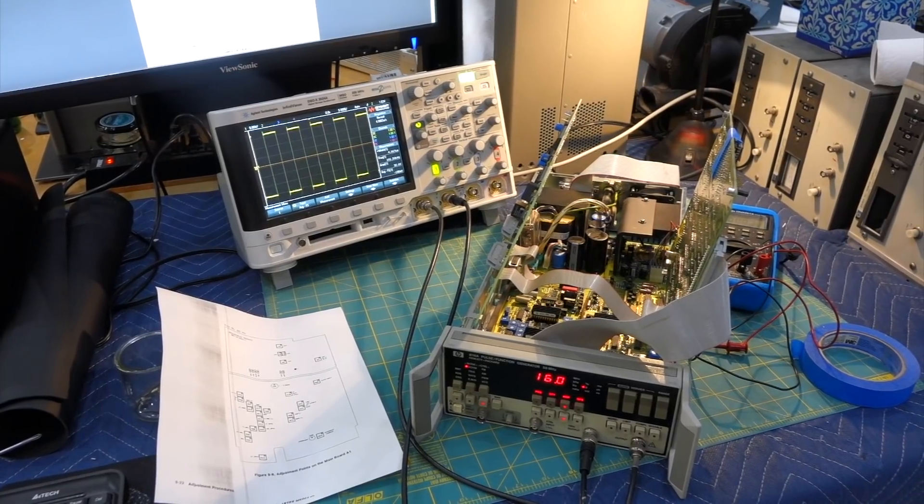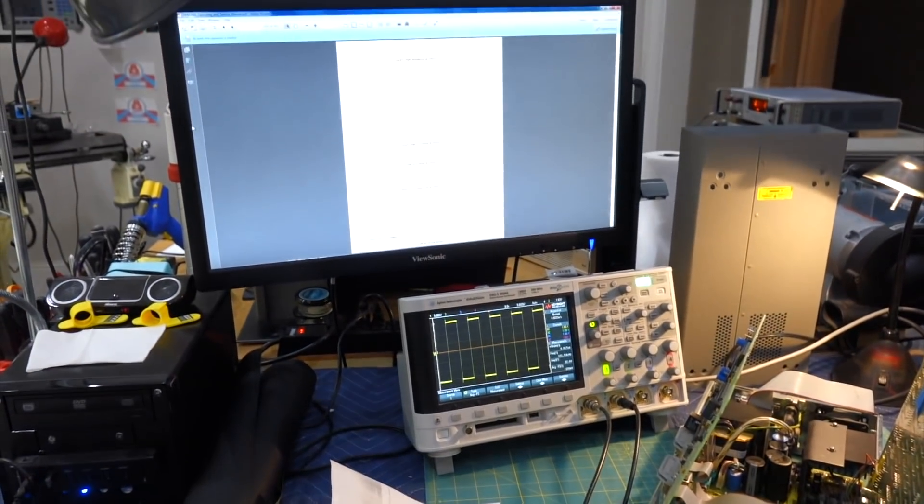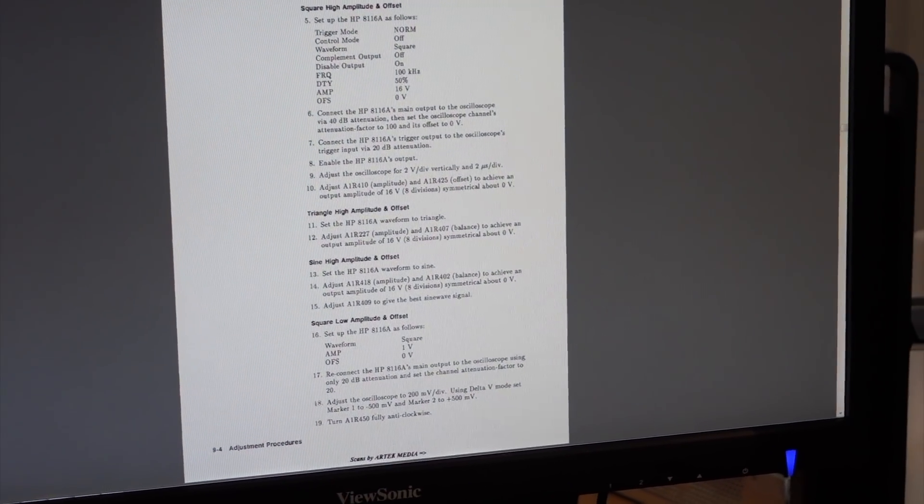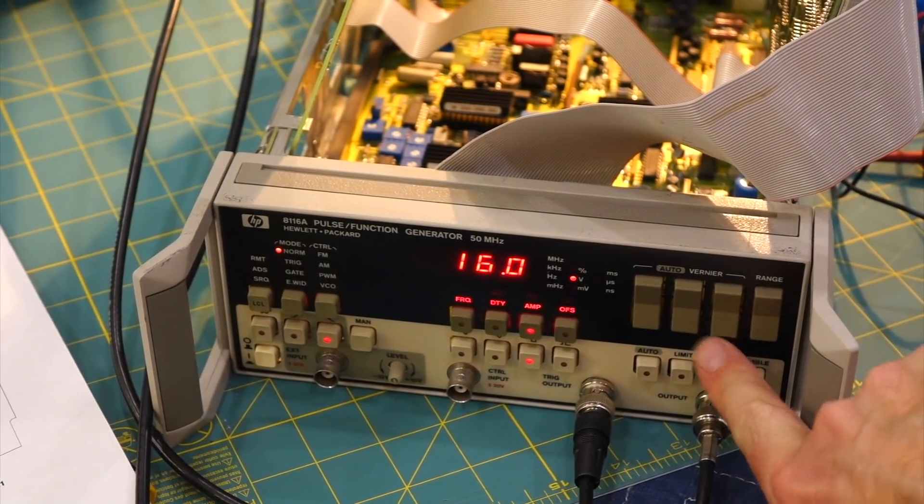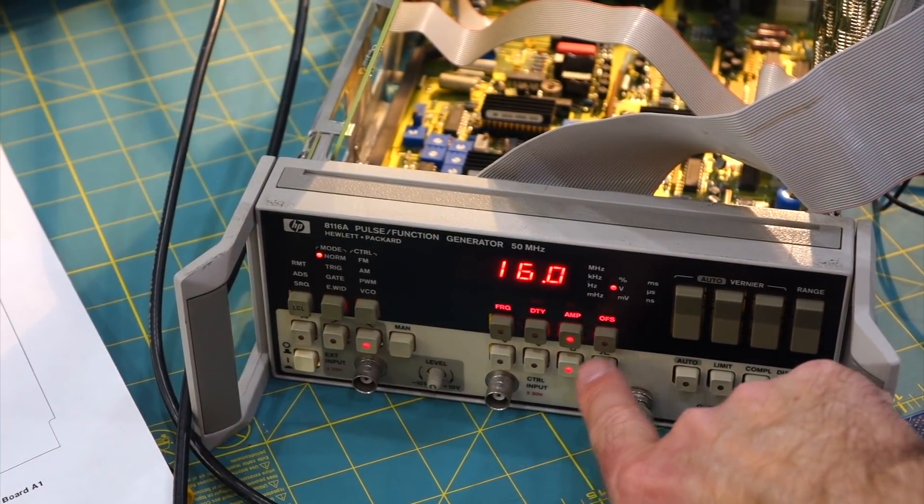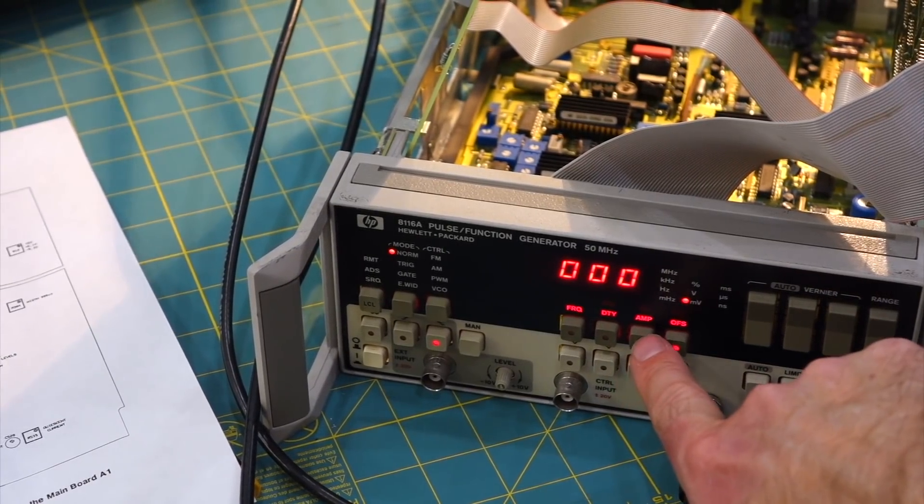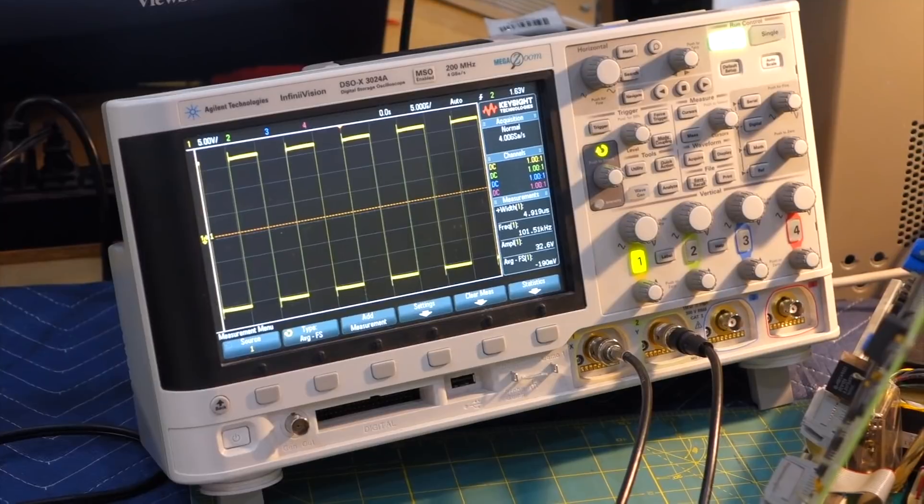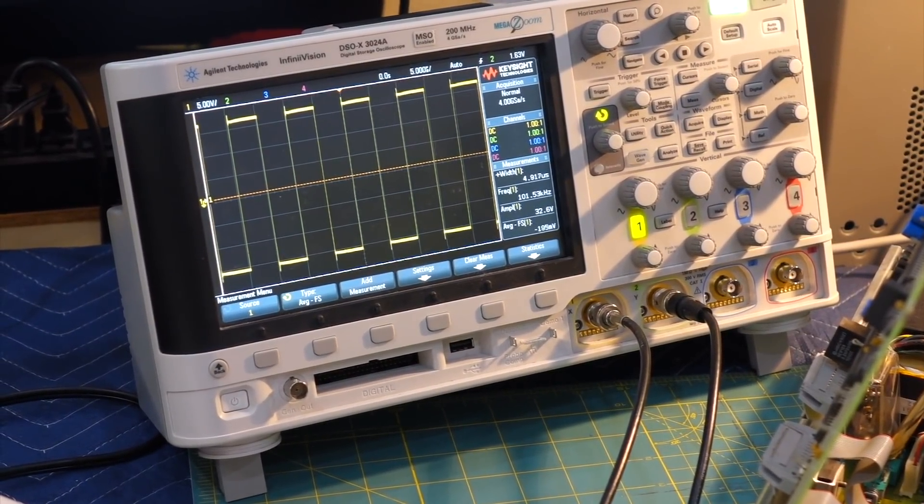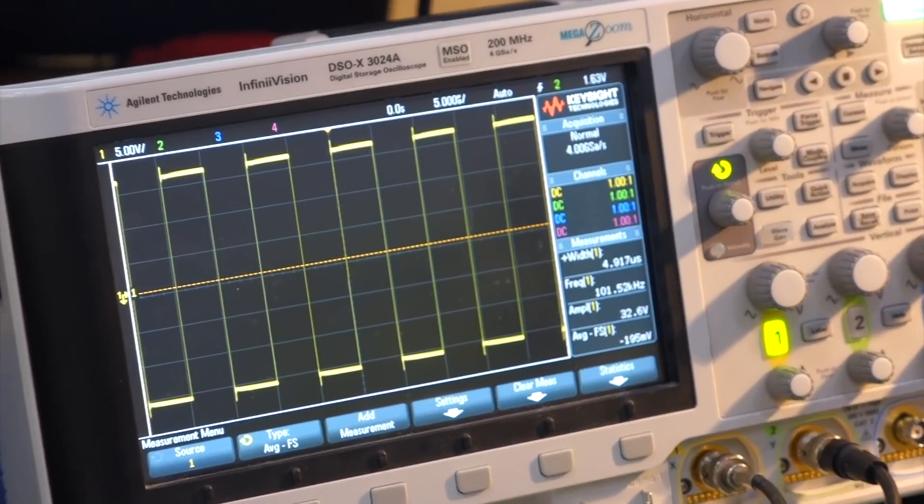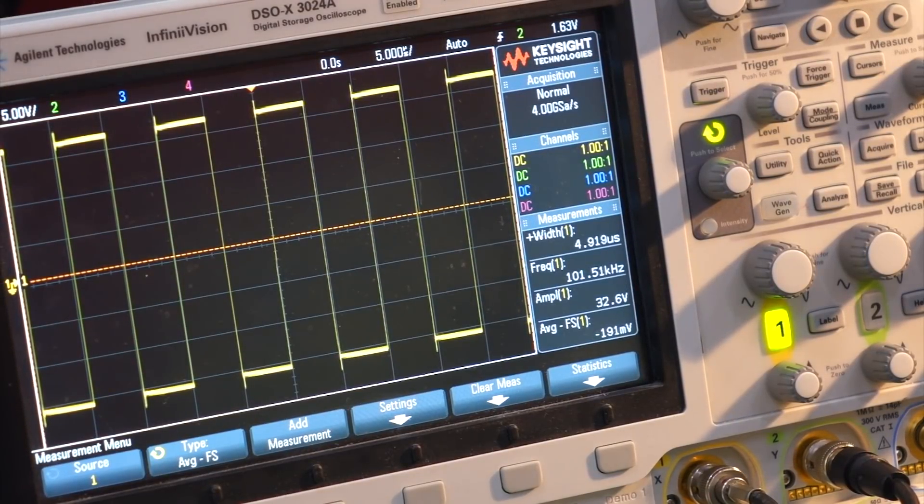The next step, and the first measurement, I'm a little bit stumped, because it says I'm going to adjust the instrument for a square wave, 100 kilohertz, 50% duty cycle, zero offset, 16 volts, which I have done. So this is one of the nice things about this instrument. The amplitude is digitally adjustable. And so is the offset. I know it's at zero, but you can have any millivolt offset you like. When I'm adjusted at 16 volts, which is probably one of the max amplitude you can do, I am getting a reading of 32.6. So do they mean half amplitude? Yes, because it cannot be that far off.